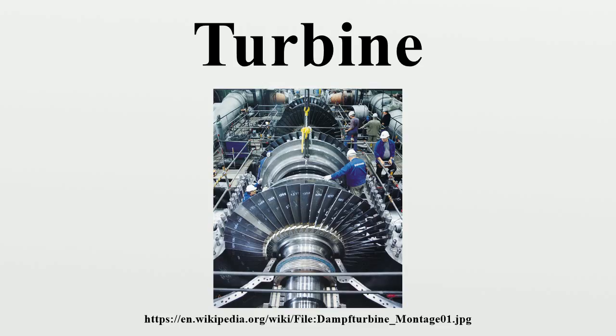Newton's second law describes the transfer of energy for impulse turbines. Reaction turbines develop torque by reacting to the gas or fluid's pressure or mass. The pressure of the gas or fluid changes as it passes through the turbine rotor blades. A pressure casement is needed to contain the working fluid as it acts on the turbine stage, or the turbine must be fully immersed in the fluid flow. The casing contains and directs the working fluid and, for water turbines, maintains the suction imparted by the draft tube. Francis turbines and most steam turbines use this concept.